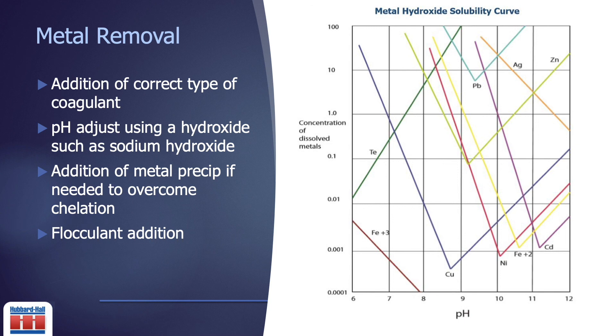Most metal finishing shops use hydroxide precipitation to remove metals from waste streams. Metals are naturally insoluble at a specific pH if there is no chelation present. The formation of hydroxide salts occurs when a hydroxide, such as sodium hydroxide, is introduced to the metal-bearing waste streams. As the pH rises, the hydroxide forms bonds with the metal, thus making it insoluble. In most cases, a coagulant will be needed to help with the removal of mildly chelated metals. Coagulants can be iron, aluminum, calcium, rare earth, or a blend of these depending on the system's needs. Added at lower pHs, when hydroxide is introduced and the pH is raised, coagulants give the metal, such as chrome and nickel, an extra bond to stabilize them in the insoluble form. You can see this with the formation of pin flock in wastewater systems.